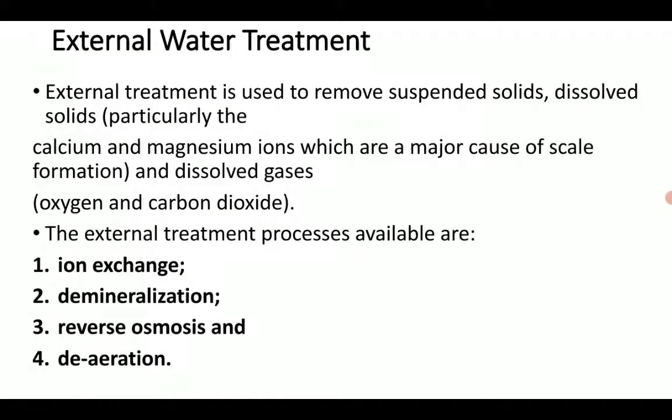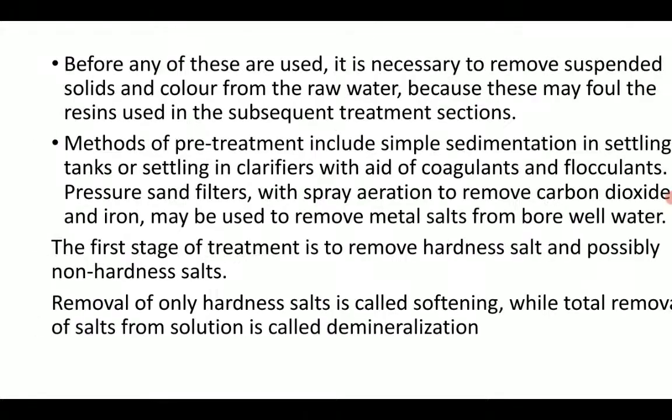So this we call as external water treatment. Before any of these are used, it is necessary to remove the suspended solids and colors from raw water, because this may foul the resin used in the subsequent treatment section. So we need to remove the suspended solids.